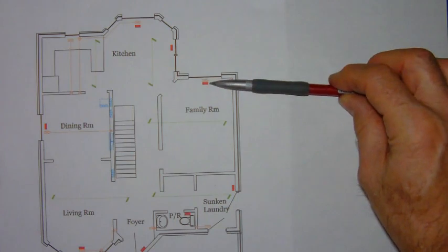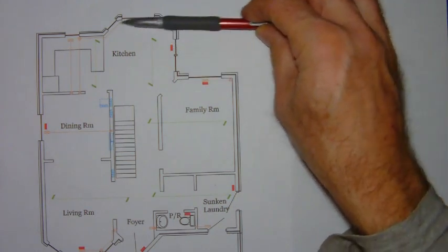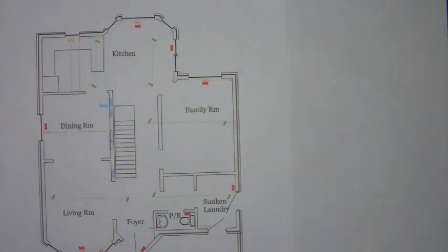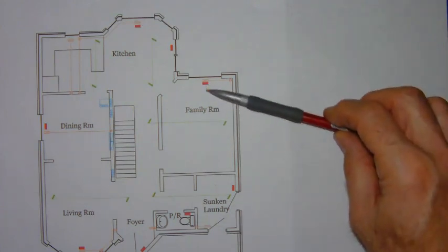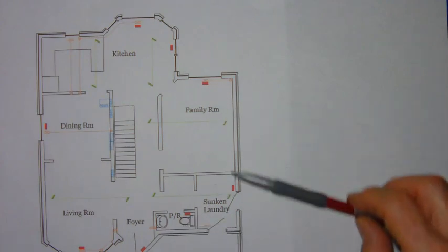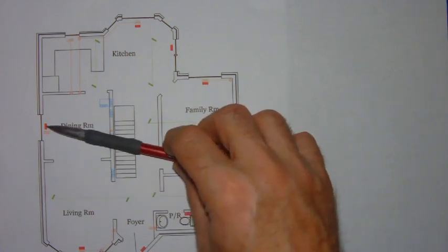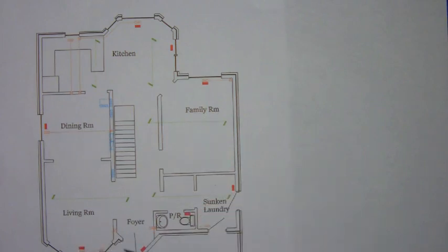If we move to the first floor, you can see that our kitchen requires 2 runs, so we've split it out between all of the glass there. All of our other rooms require 1 run, and so we've installed these runs, if we can, under the windows, near the door. In the case of the powder room where there is no window, we try to locate it in the most convenient location.